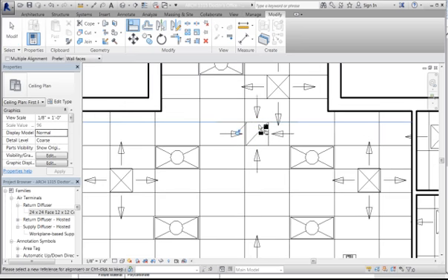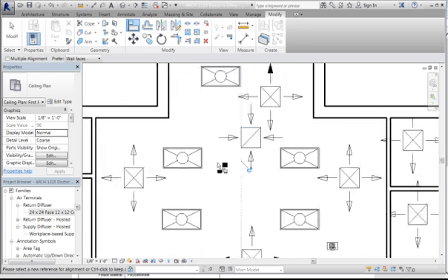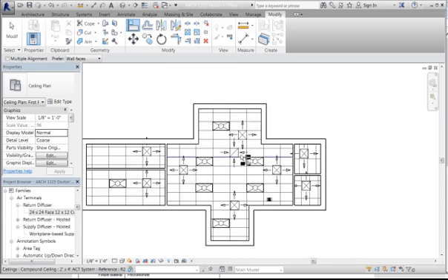So I'm going to line that up there so it's nice and neat. I just showed you how to put it in there. I'm not thinking about where it's at. You don't want one right next to your supply, or else the air that's blowing out here will go right into there. So think about that when you're laying this out, okay? Keep it a little bit of a ways from your supply. Also your thermostat will usually be near your return air because that's the air you want it to measure.